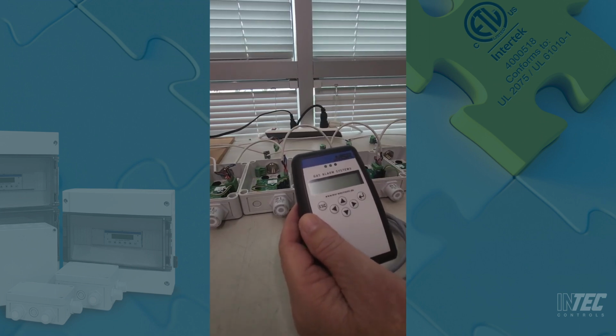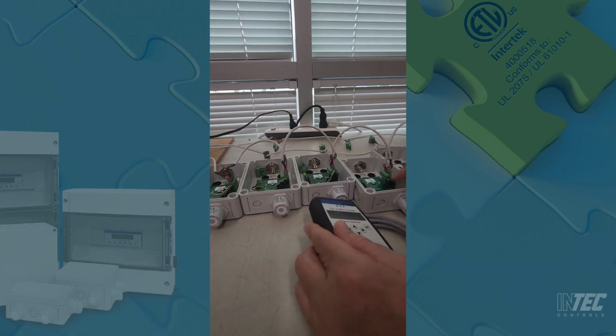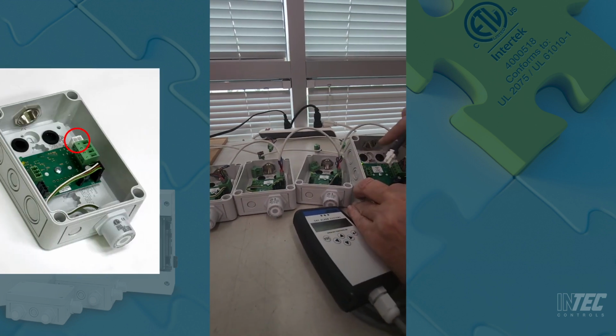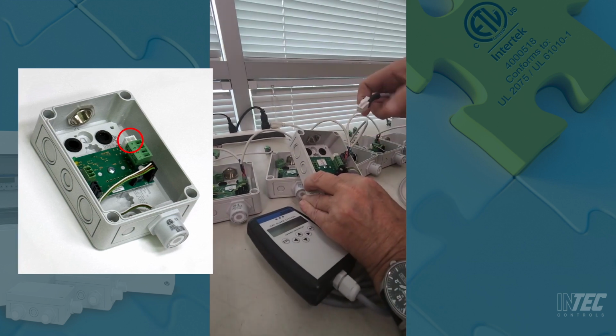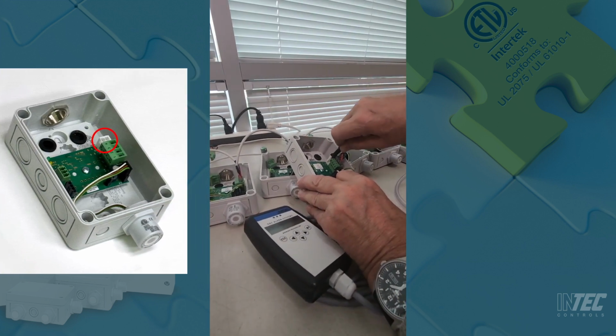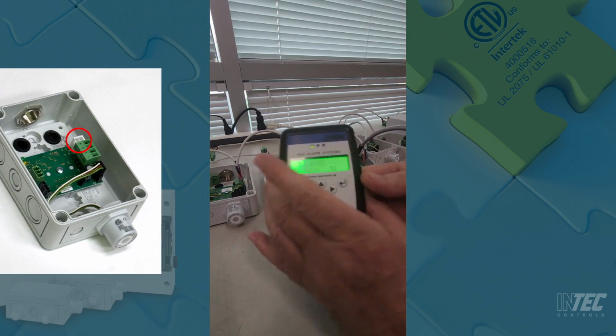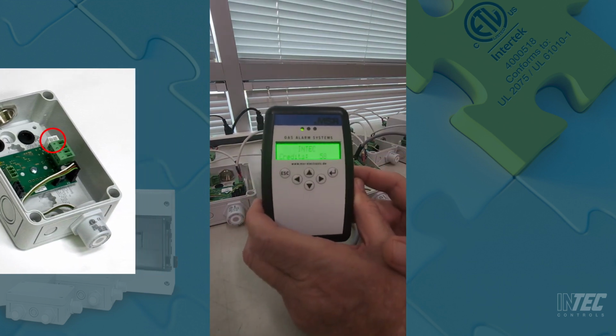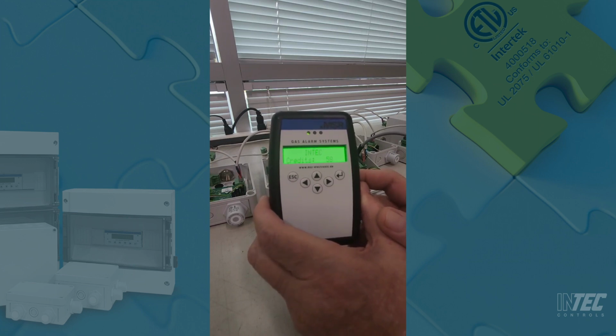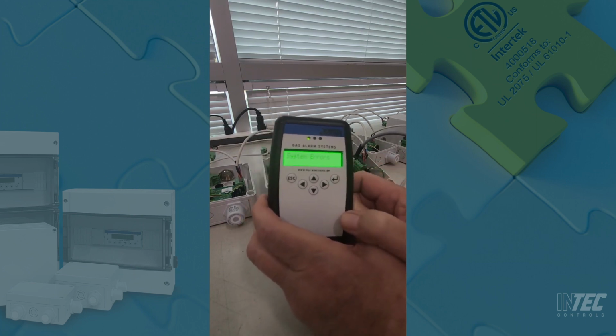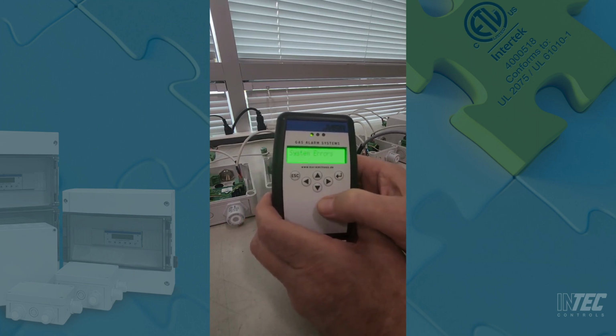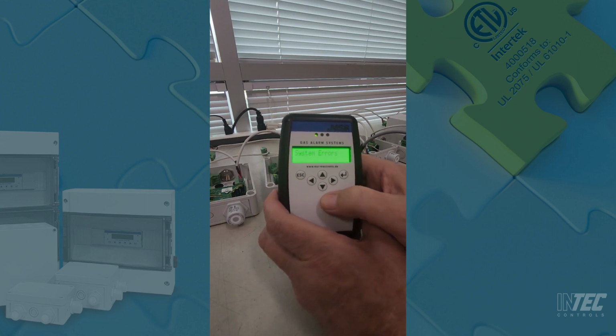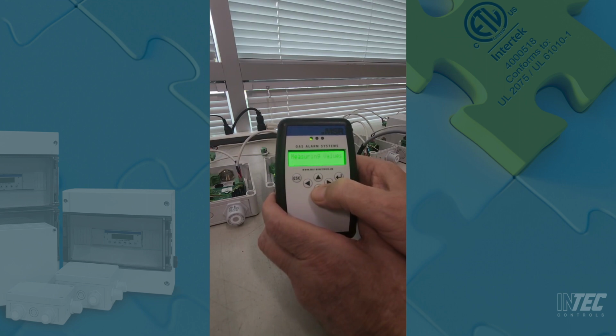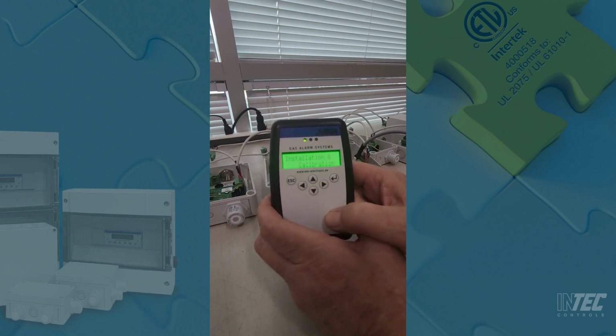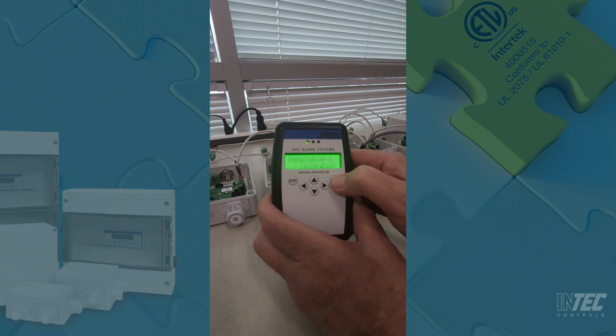First you're going to take your service tool and plug it into the service port on the sensor. You can see the white 4-pronged service port right here. Just connect, and you'll notice that the handheld tool will energize. In order to get to the menu, you're going to hit the enter button. You're going to enter calibrate. We must put the unit into service mode, so we're going to arrow down until we see installation and calibration. We're going to hit the enter button.